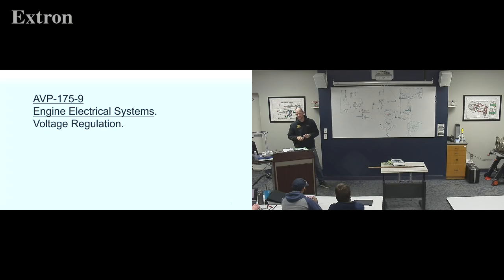And so there's no difference in ohms? It's not ohms, because what your voltmeter does is it puts a voltage in, but it's going to slowly raise the voltage. Once it gets to the point where it says this is enough, it starts just passing the current through. So it's not going to hold as steady on your ohm meter.